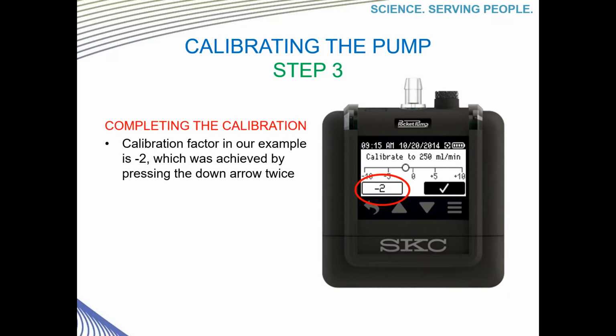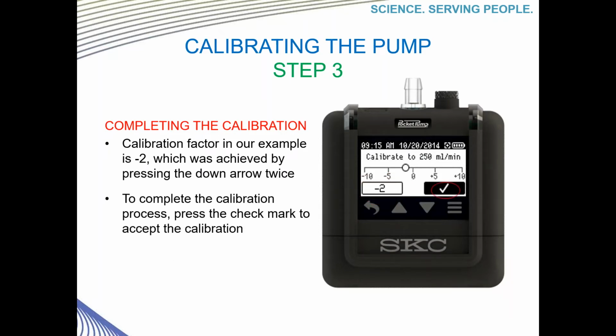In our example or illustration here, our calibration factor is -2. What that means is that we had to slow the pump down by pressing the down arrow twice in order to make the calibrator flow rate reach our desired 250 milliliters per minute. Now to complete and accept the calibration, simply touch the check mark on the display. You have now completed the calibration in 3 simple steps. So in just a matter of a few minutes, we have just performed the basic flow adjustment and flow calibration normally required to get started doing your air sampling.